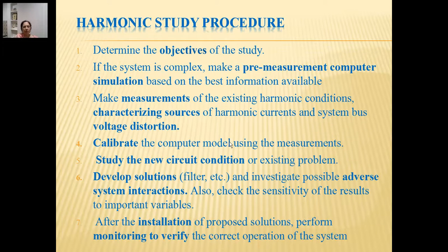There is a procedure which is followed for harmonic study. First we have to determine the objectives of the study, that is, for what purpose we are going for this harmonic evaluation; that must be known. If the system is complex, make a pre-measurement computer simulation based on the best information available.